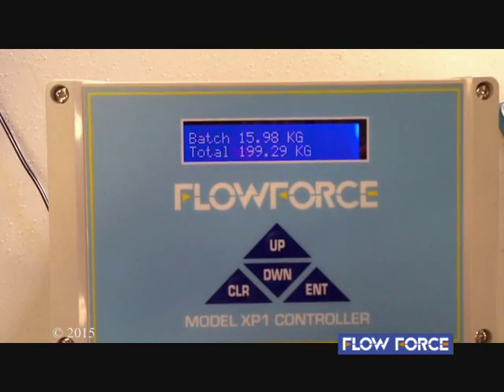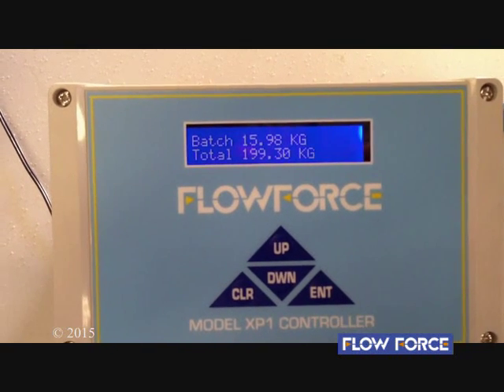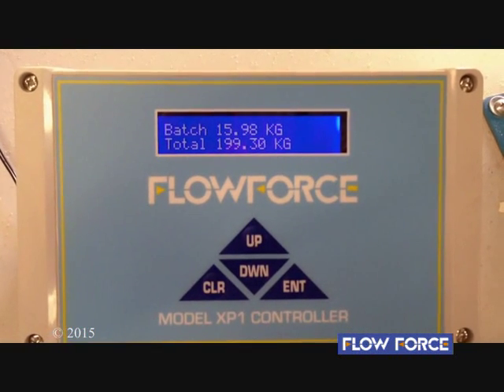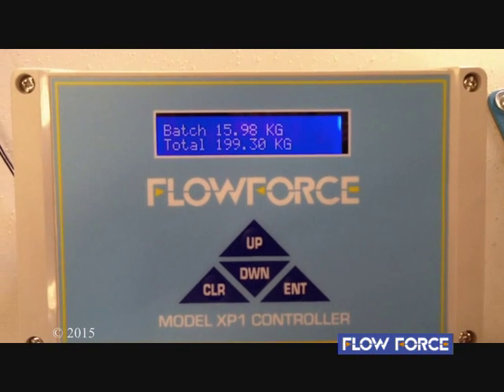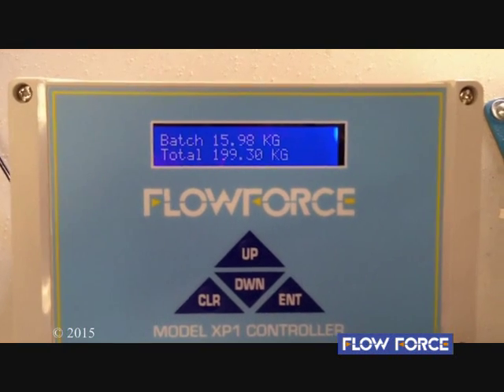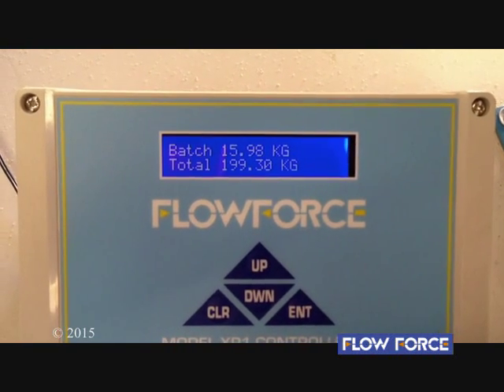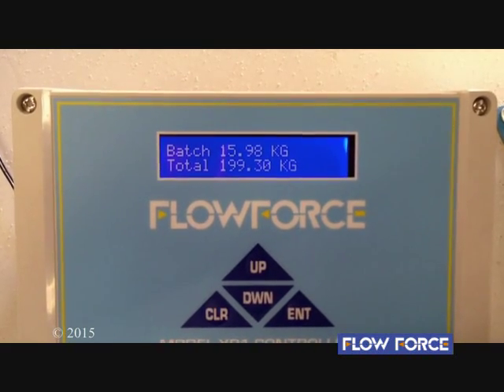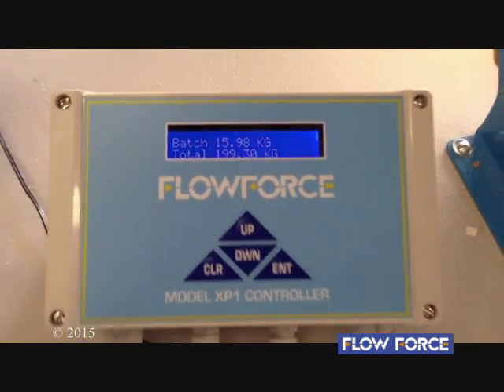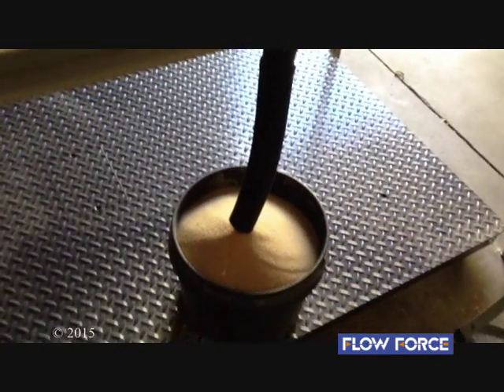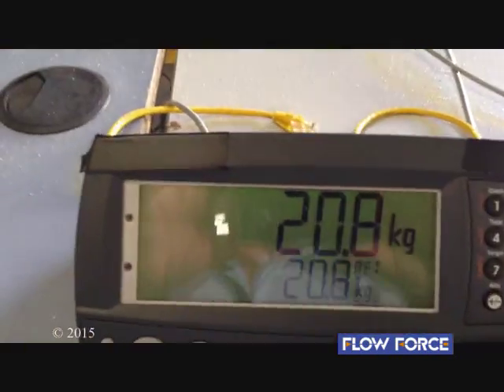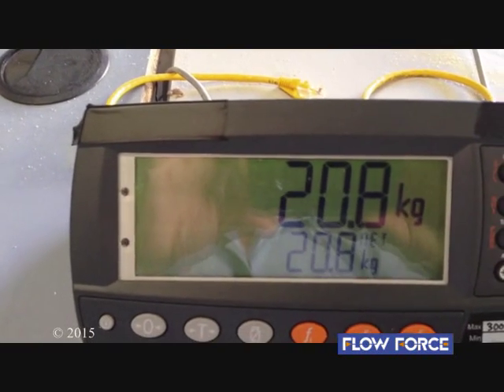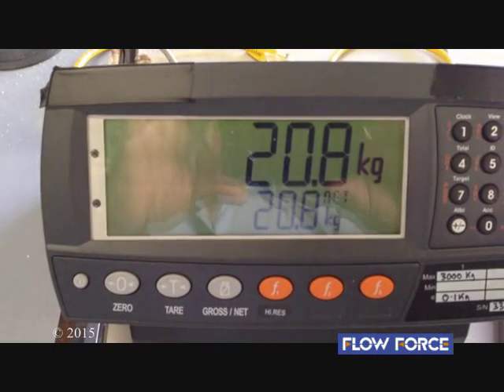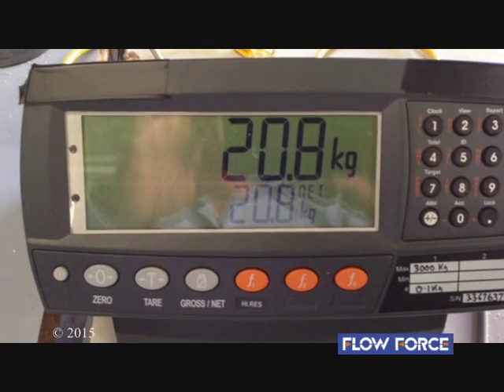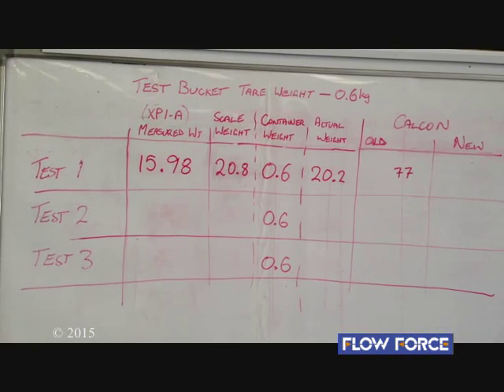Okay, batch is complete, and we'll take the reading from the XP1 controller of 15.98 kilograms, and we'll check the weight from our container on a set of scales. So we'll place the container on our scales, and we see we have a reading of 20.8 kilograms, and so we'll mark this up on our calibration sheet.